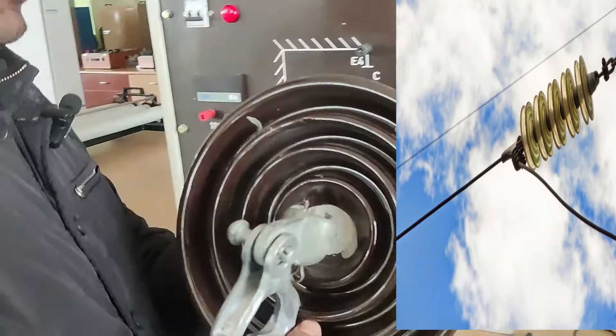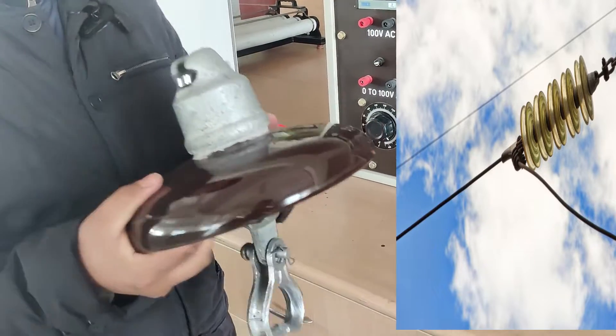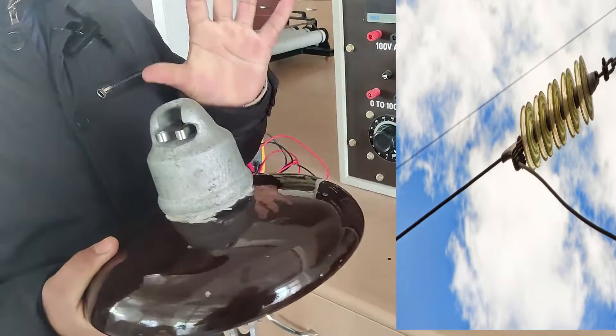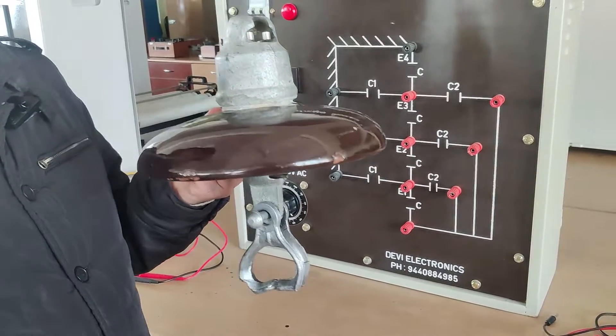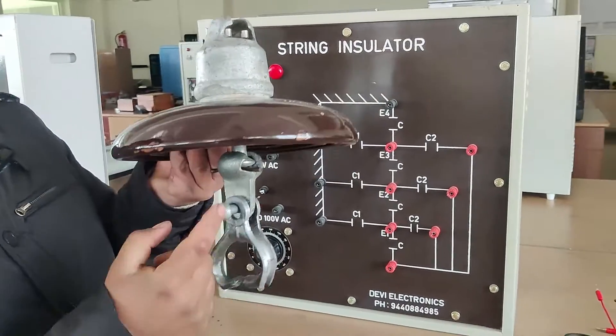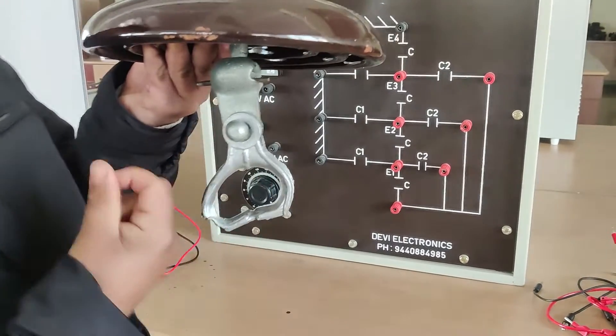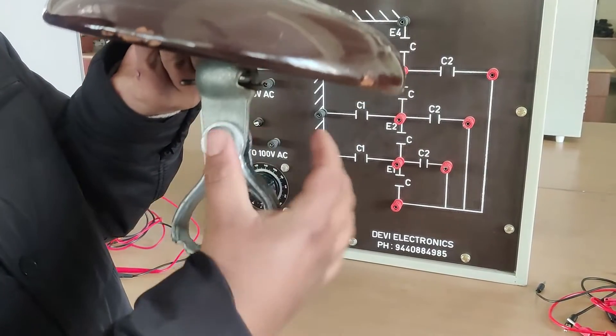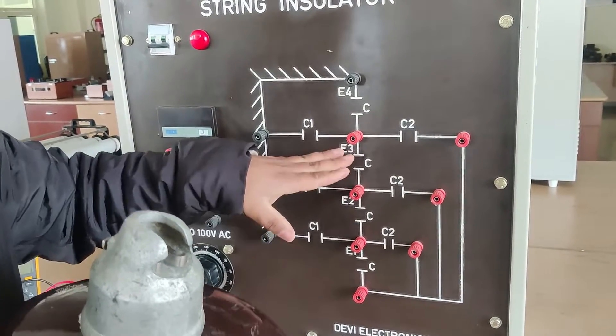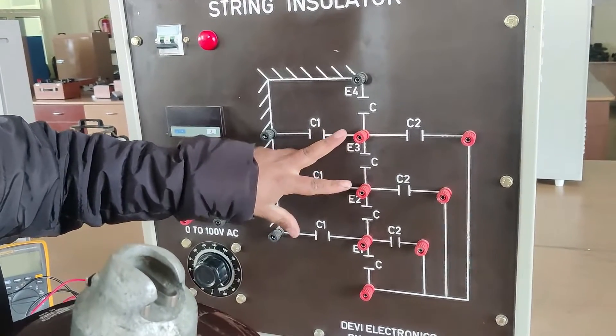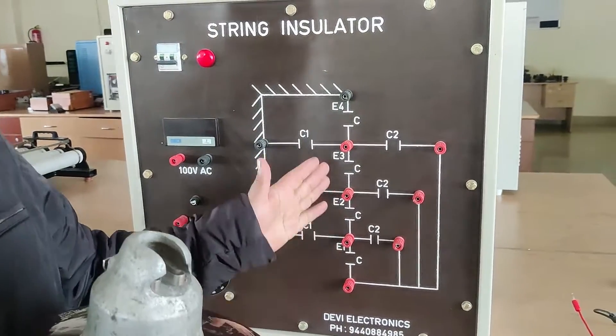In practice in transmission systems, you may have seen suspension discs. One disc is rated for 11 kV — that is the level of insulation built in. If we have a phase voltage of 33 kV, we need to use three discs and cascade them. Between two discs there is a metallic pin, and the capacitance exists between two metallic pins because the insulator disc in between acts as the dielectric medium. We call these the main capacitances.